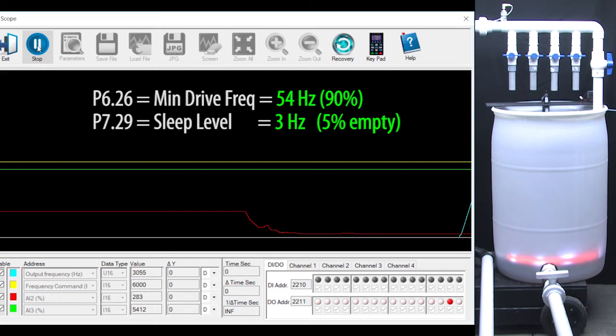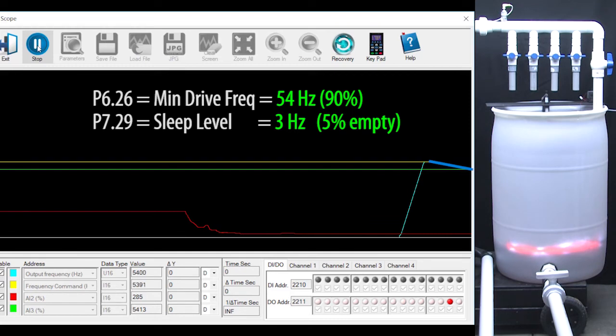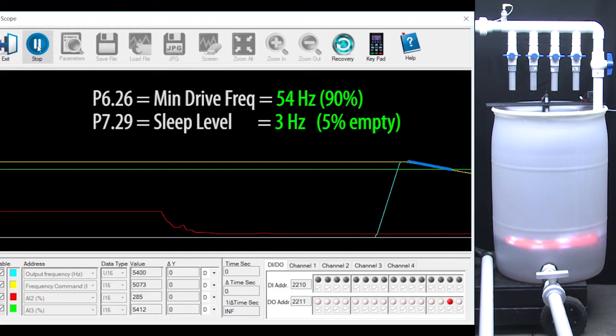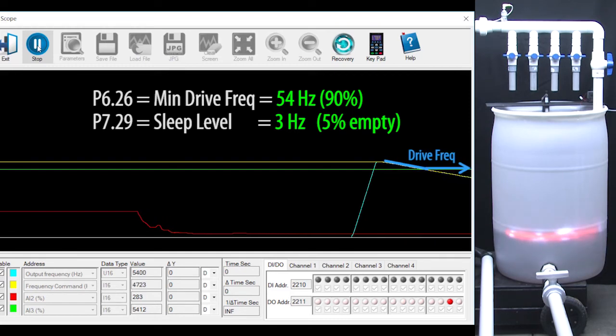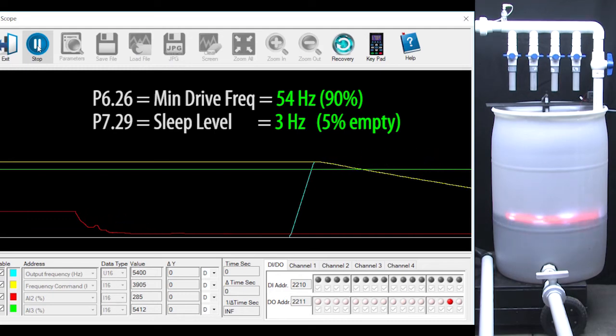So now as the water level rises and the motor starts to slow down because the sensor value is getting smaller, when it hits the high minimum speed we just set, the motor just stays at that high minimum speed even though the command frequency set by the sensor is still falling.